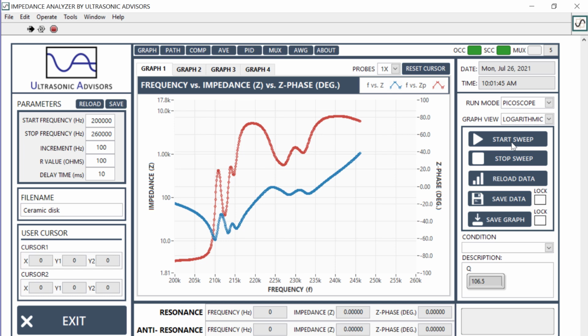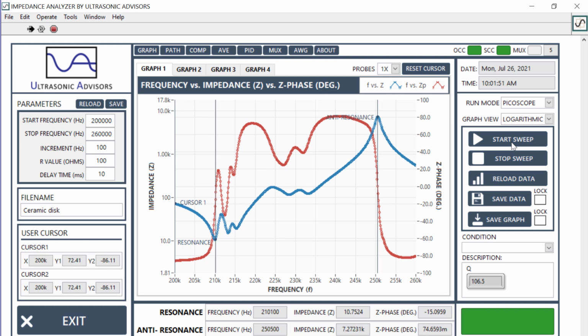What this shows is how you are holding the crystal extremely changes the results. The result before was 4 ohms, now it's 10. So the impedance jumped by a factor of 2. We see a lot of spurious behavior, which is going to be a large contributor to this incorrect holding. It just generates other modes of operation due to holding it in that position. It's semi-clamped. There's some stiffness involved with clamping, and many factors then come together to cause spurious modes and hence larger damping, which causes a larger impedance and inconsistent results.